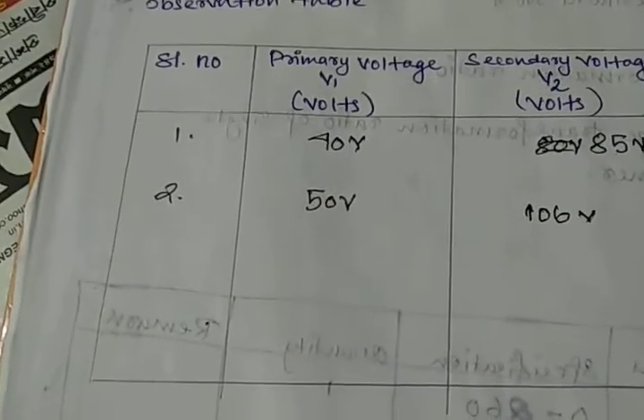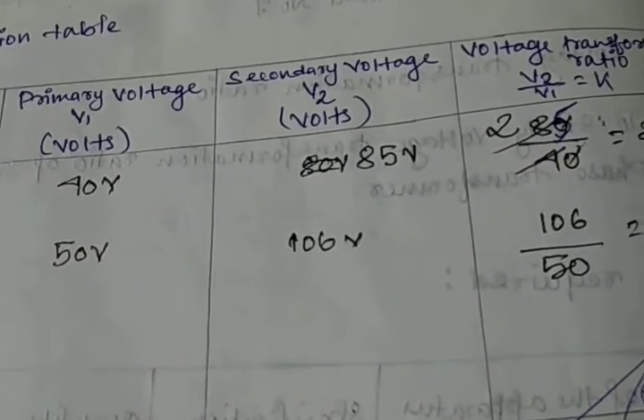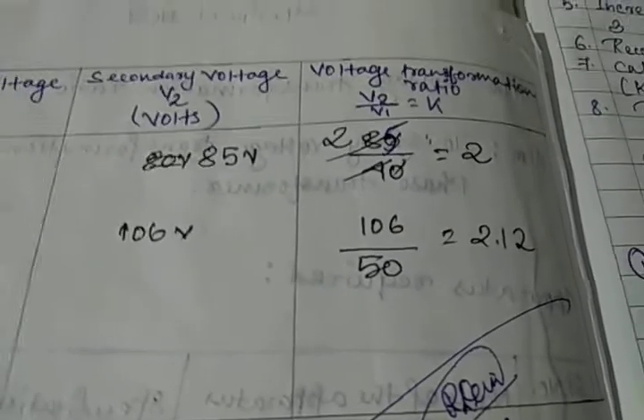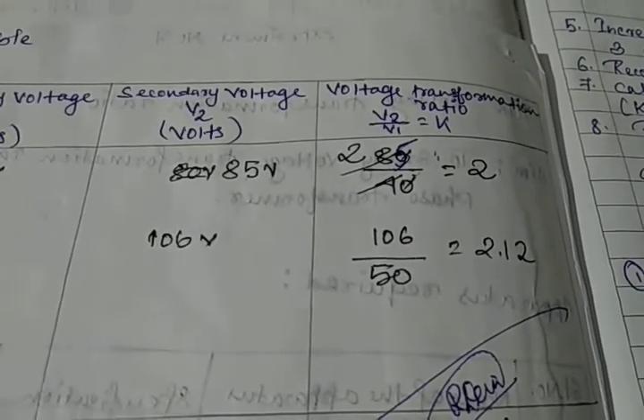For the second set, we have applied 50 volts as the primary and we are getting 106 volts as the secondary voltage. Here also we are getting 2.12 as our voltage transformation ratio, V2 by V1.